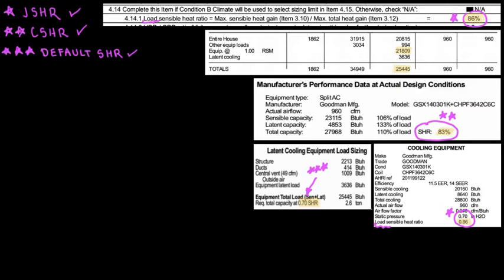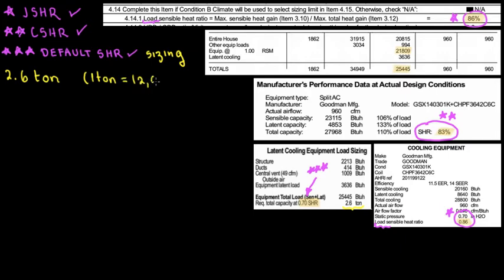Let's understand the default sensible heat ratio with a simple calculation. The main reason for this default sensible heat ratio is for sizing purposes. We see 2.6 ton here. When we're talking about tonnage, we remember that 1 ton equals 12,000 BTUs per hour — that's the nominal tonnage. So why is it 2.6 ton? Because we're using the default sensible heat ratio to size this unit based on the load calculation.